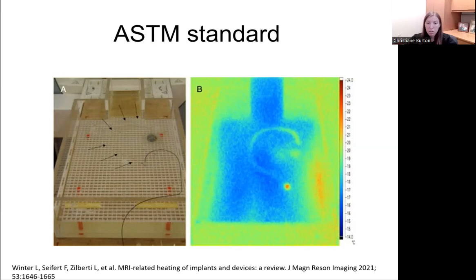These images show a gel-filled torso phantom for evaluating heating of a pacemaker and wire shown in the arrows. A black temperature probe is attached to the tip of the pacemaker lead. On the right, a heat map assessed by an infrared camera after RF excitation shows a temperature increase at the lead tip.